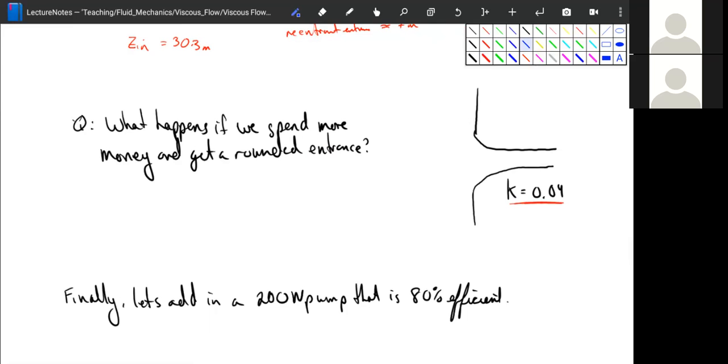0.73. And remember, when we do this, the fluid's very happy because it just goes around the bend and enters the pipe. Because it can take gentle bends very easily. It can't take 90-degree bends, but it can take gentle bends very easily. So we don't get any of that initial flow separation. We don't get the vortices. We don't get the area decrease. Everything is much more well behaved.